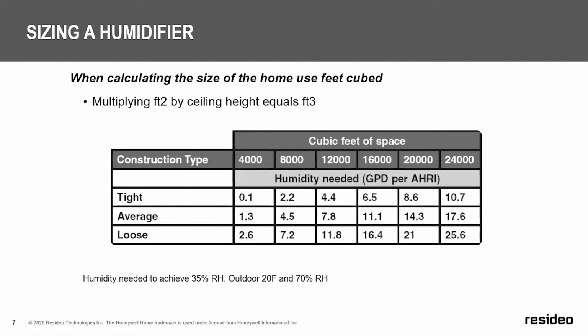Sizing a humidifier is sometimes tricky. And in reality, the best thing you can do is take into account the basic tightness of the construction. Is the thermal envelope average, tight, or rather loose? And then the square footage in the home multiplied by the height, so that you can get the cubic feet of space that you're trying to cover.